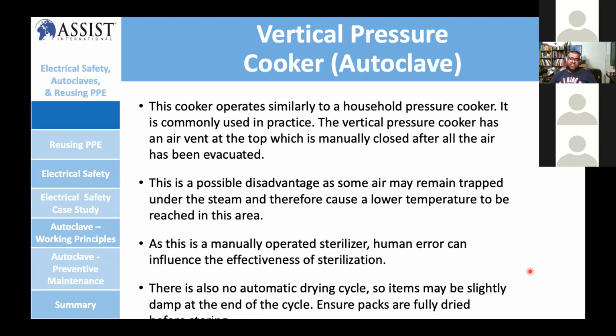Then the vertical pressure autoclave, which we used to call a cooker autoclave. It operates like a household pressure cooker and is commonly used in practice. The vertical pressure type uses an air vent on the top, which is manually closed after all the air has been evacuated. The disadvantage is that air may remain trapped inside the steam and cause a low temperature to be reached in this area. Certain areas are not fully covered because these are manually operated, and sometimes because of human error, you're not going to get full sterilization. At the same time, it does not have an automatic drying cycle, so items may be slightly damp at the end of the cycle. So you have to dry them before storing.